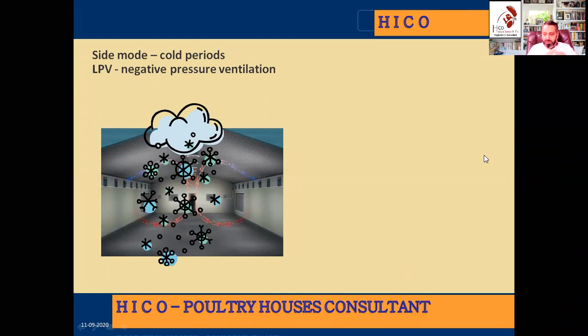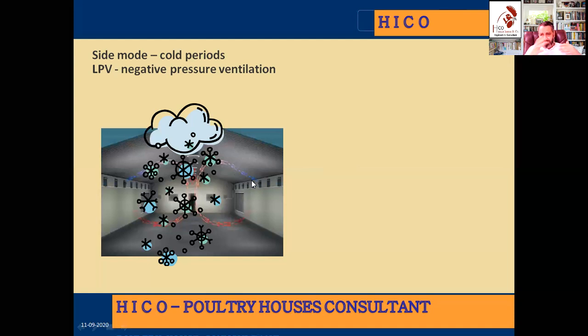Looking at this picture, you can see side mode ventilation. The minimum ventilation is also a side mode ventilation but it is timer-based. Keep in mind that in timer-based ventilation the fan runs on a timer, while in side mode ventilation the fan runs thermostatically. Side mode ventilation occurs when the outside temperature is slightly higher — one, two, or three degrees — than inside the house.